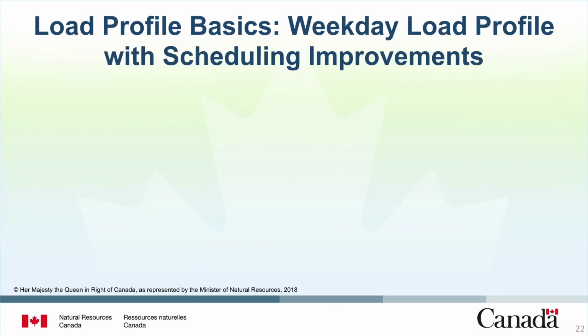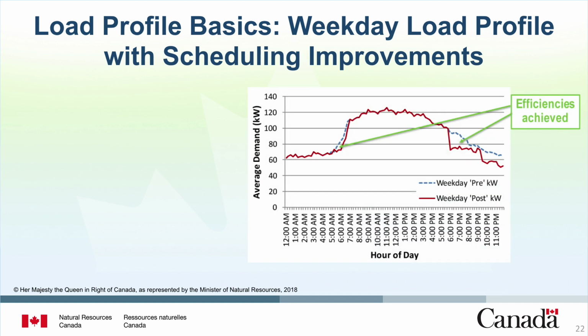Now that we know how to read load profiles, we can use them to help improve energy and water efficiency. Load profiles can be used to determine opportunities to reduce load with scheduling improvements. Let's use an example with a weekday load profile. This weekday load profile shows that efficiency improvement opportunities are possible by adjusting the operating schedule.